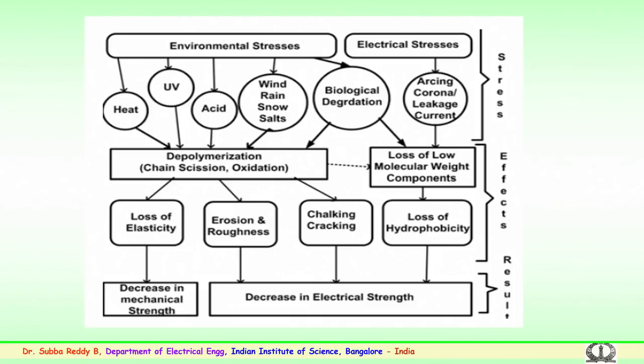Similarly, snow, fog and mist are more serious, as they settle over the surface on top of the contaminants already existing over a period of time. During the monsoon season, if rain, snow, mist or fog makes the surface wet, it becomes conducting with higher leakage currents. Depending upon the surface conditions, dry bands and wet bands form because of this uneven spread of contaminants. So, here again the surface could degrade because of these conditions.